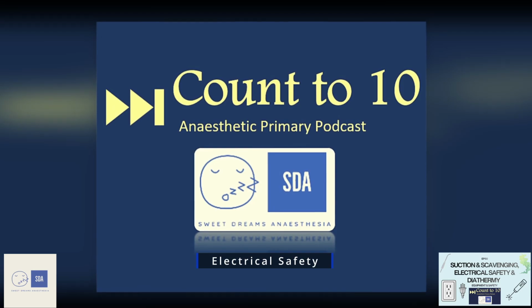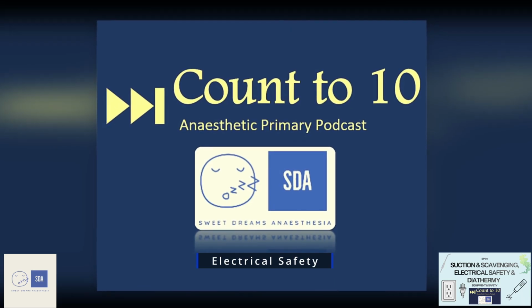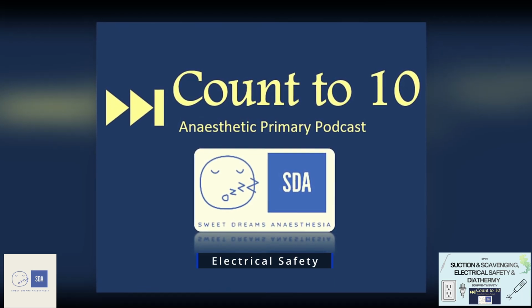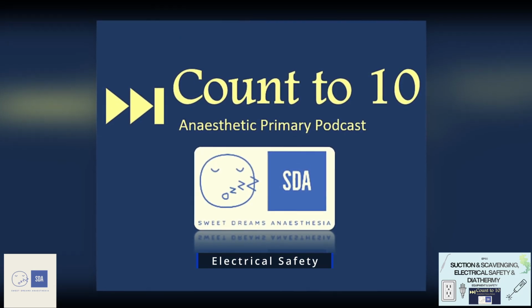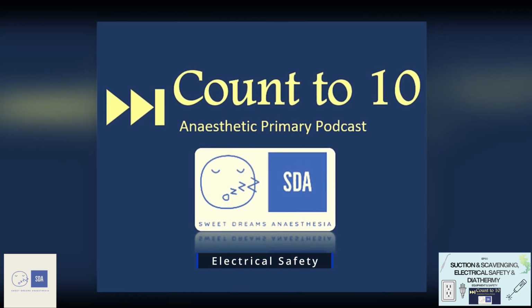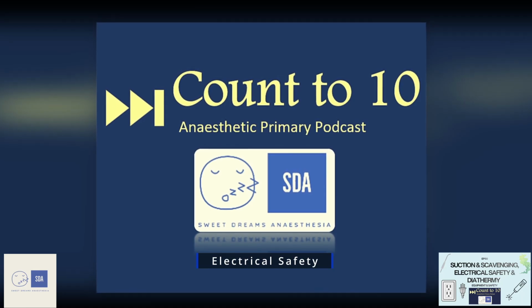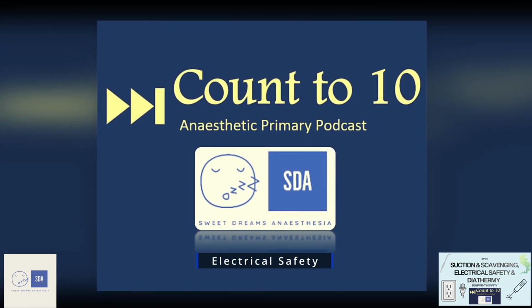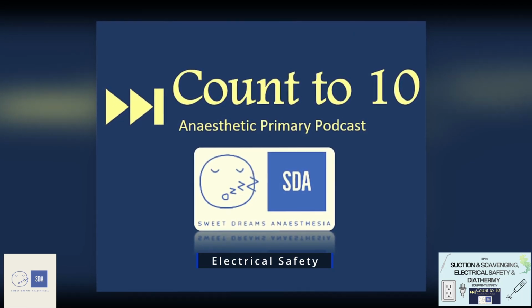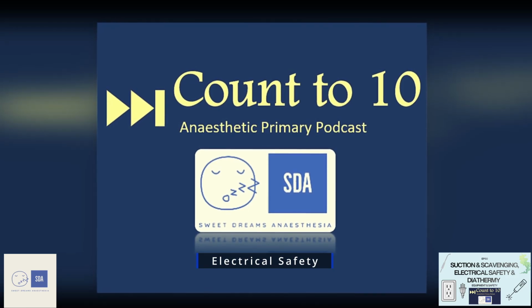And this is mandatory in the operating theatre because it's the only type of safety system that protects against microshock. So therefore, it's a must, and you can see your EES in your operating theatre as usually a green knob at the back wall in your operating theatre room.